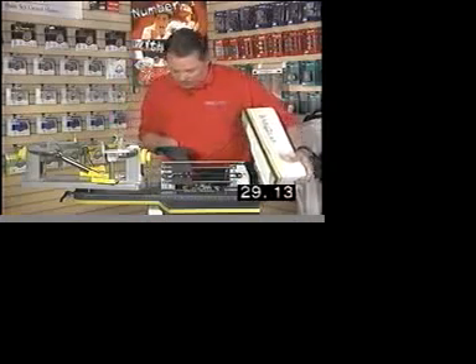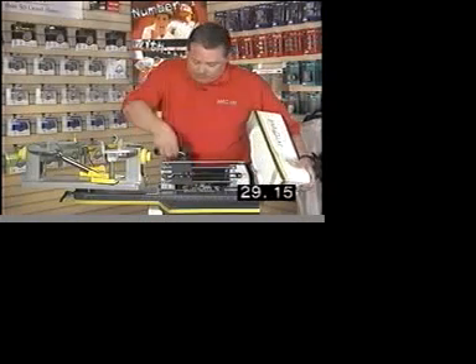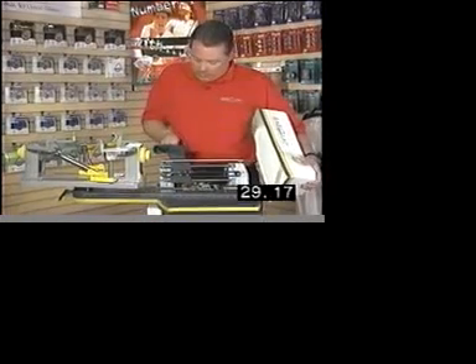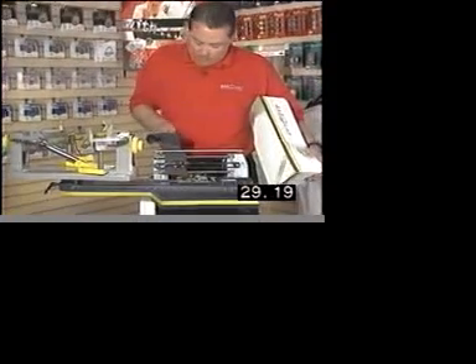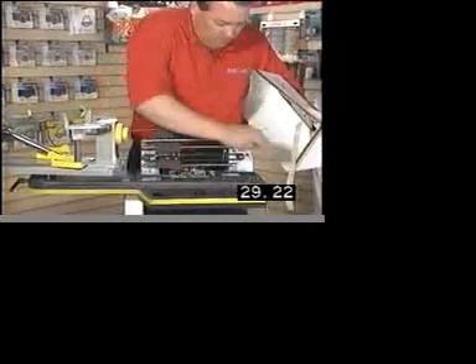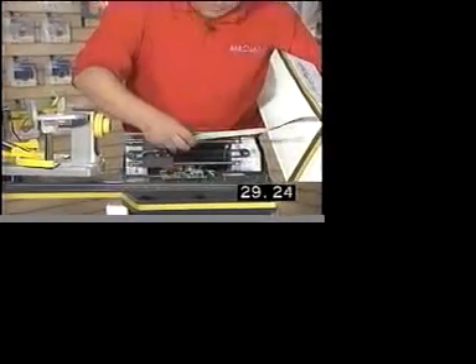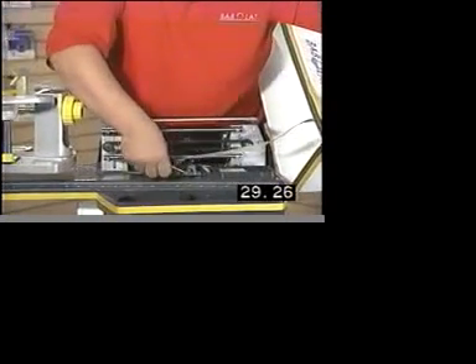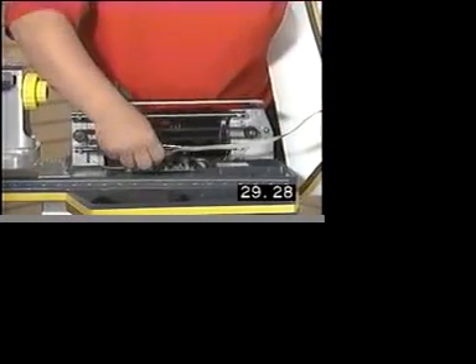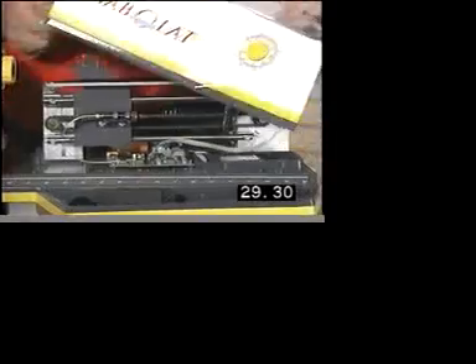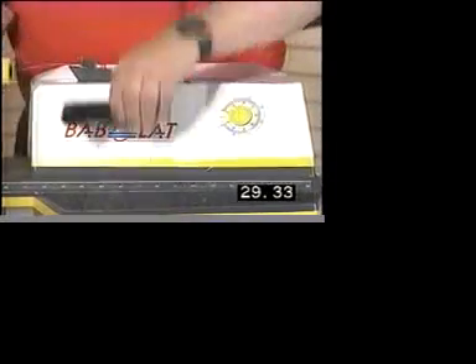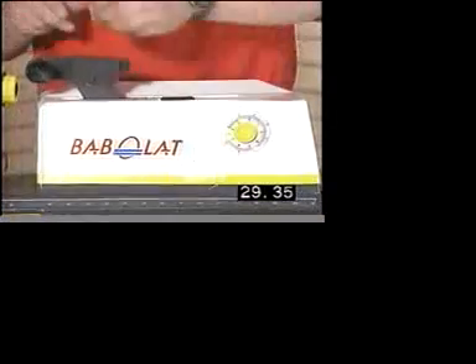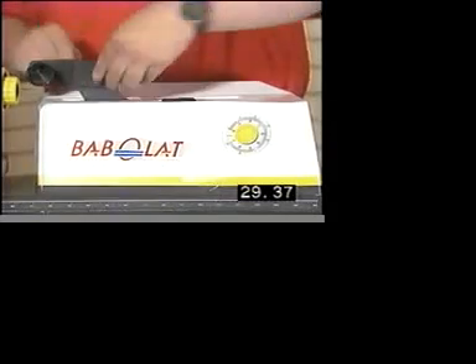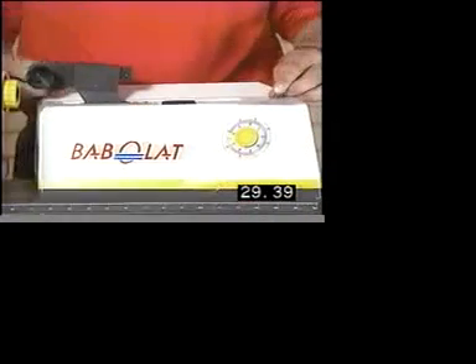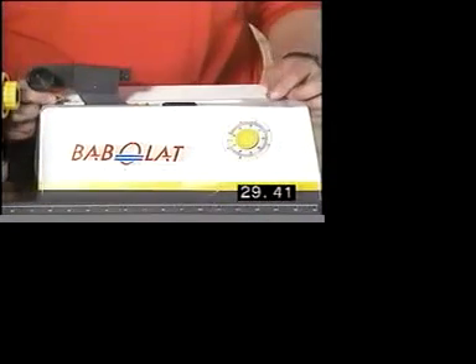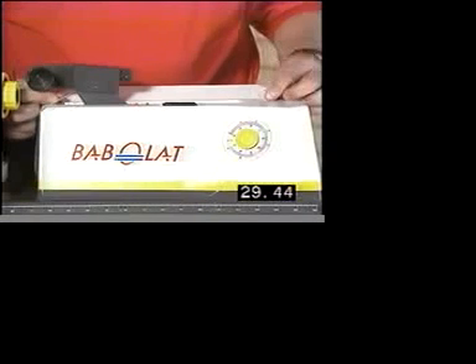After you finish calibrating your machine, you want to put it back together. Once again, you're going to pop the center pin out so you can take your pulling head off. You're going to plug your cover back in, once again making sure that the wire comes out to the right and you're not forcing it. Set your cover on, push your pulling head back on, and then put your screws for the cover end back in. That's all there is to it.